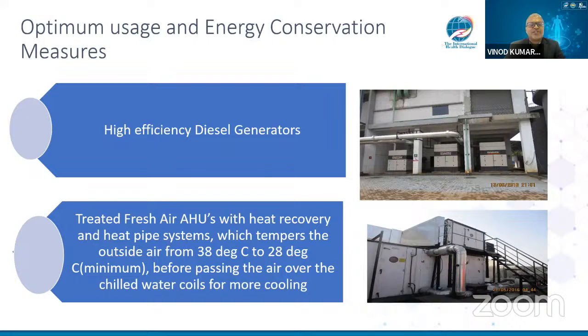Another important aspect is the use of treated fresh air handling units, which generally have a heat recovery system. I talked about waste air going out of the hospital through extraction or ventilation, which is generally cold. Now we can use heat recovery wheels in the treated fresh air units, whereby you take the chillness from the air being extracted outside and put it into the fresh air through the heat recovery wheels. That way you are able to temper the outside air from 40 degrees to 24, 25, or 28 degrees, depending on your selections, for the fresh air supplied across the building.